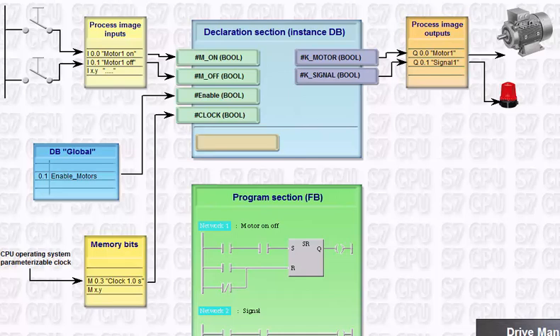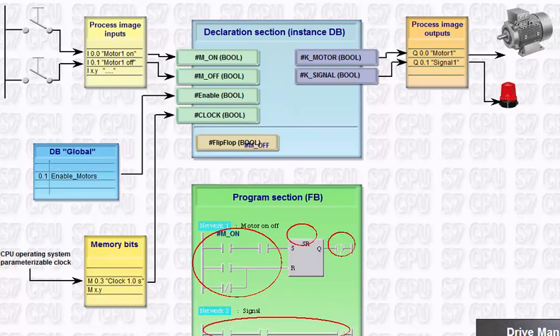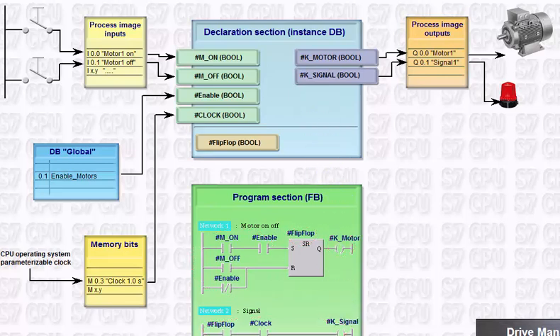The status of the storage element in the program must also be maintained after terminating the motor block. A static variable is therefore created in the declaration section of the FB. For an FB, all parameters, temporary and static variables are stored in the instance data block. The operands of the user program used in the block are exclusively switched via the symbolic name of the block parameter and static variables of the declaration section of this block.